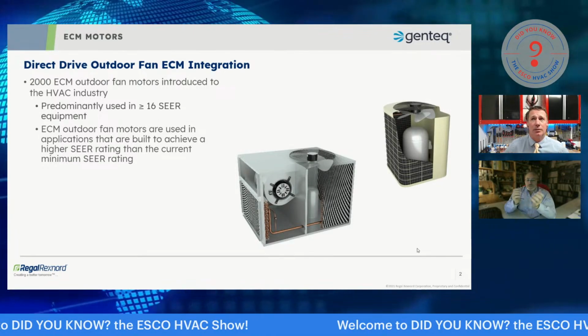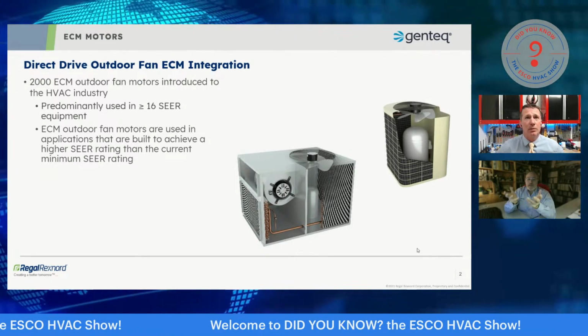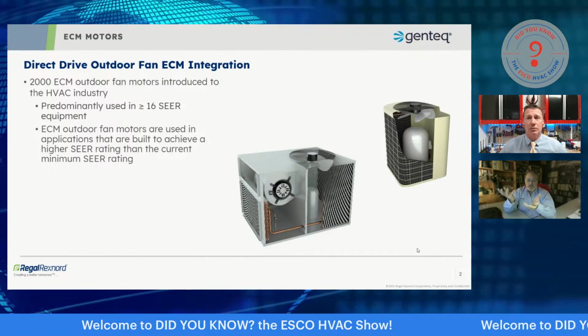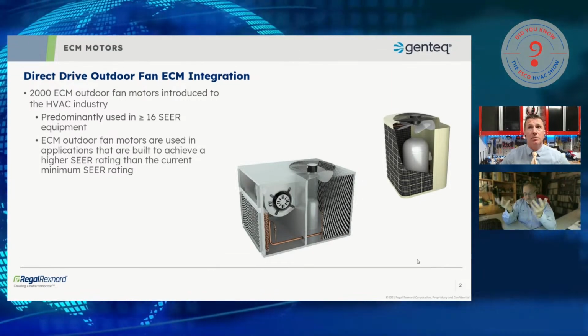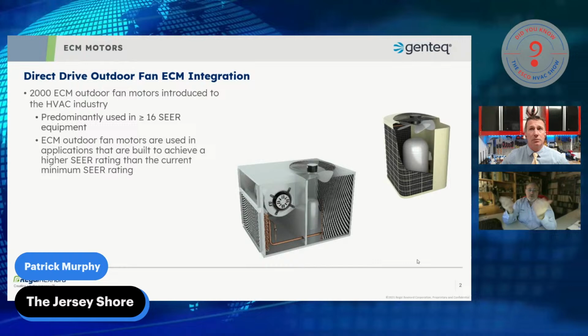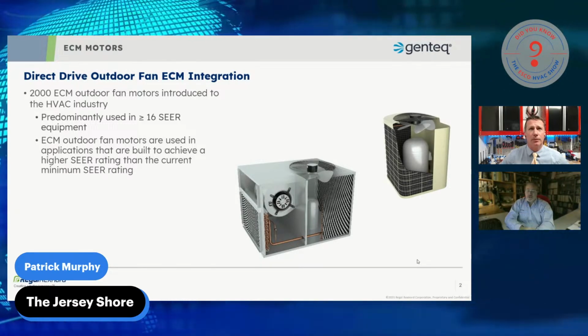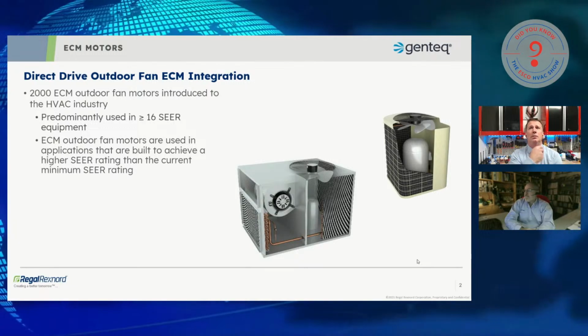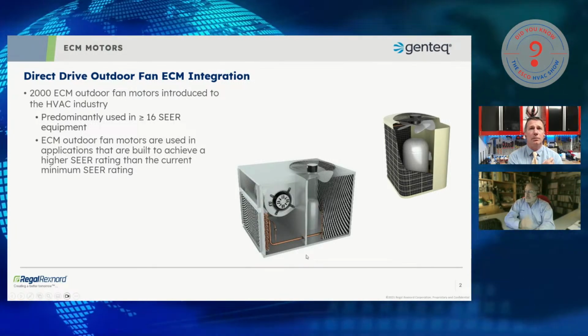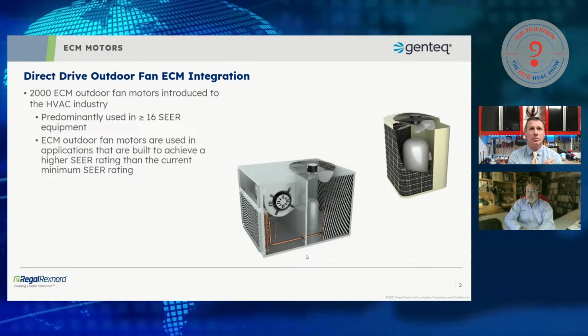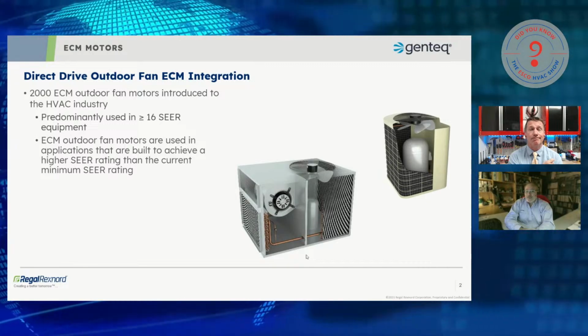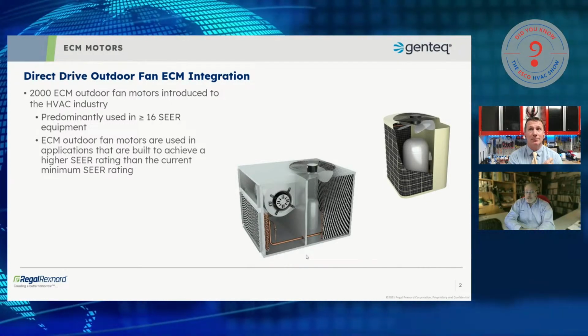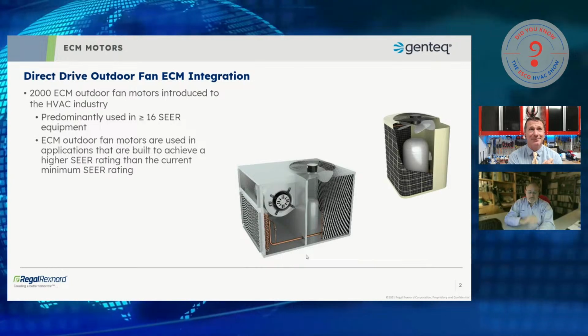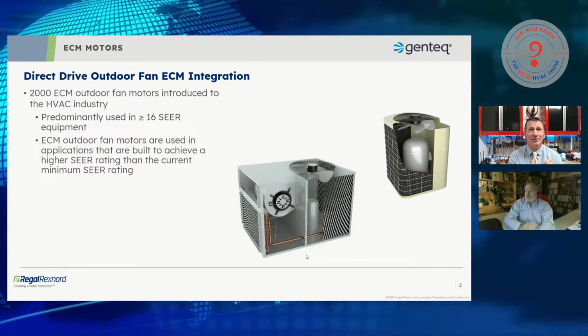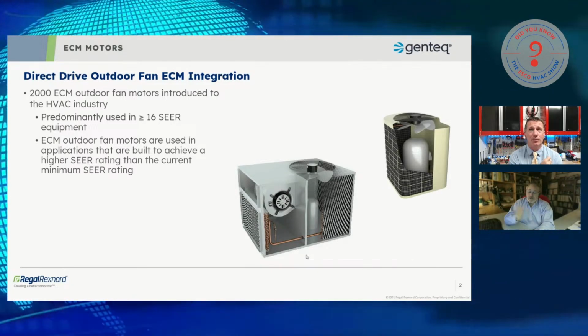Obviously, there's a difference. The OEM has to weigh the value of energy efficiency versus the cost of the motor, compared to other components or changes they can make to hit those SEER points. So around 16 SEER is where we typically see these motors. They're used in applications to achieve SEER ratings today that are higher than the minimum requirement for most regions of the U.S. And we'll cover that in a moment. But I wanted to hit that first, again, introduced in 2000.